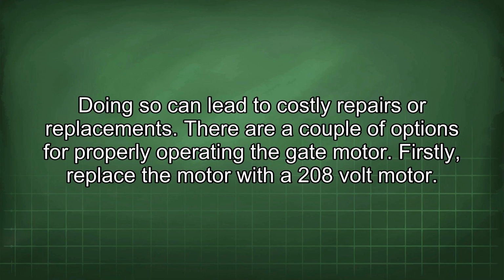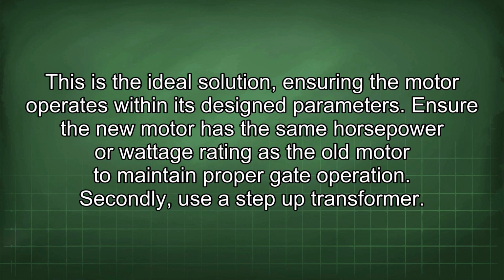There are a couple of options for properly operating the gate motor. Firstly, replace the motor with a 208-volt motor. This is the ideal solution, ensuring the motor operates within its design parameters. Ensure the new motor has the same horsepower or wattage rating as the old motor to maintain proper gate operation.